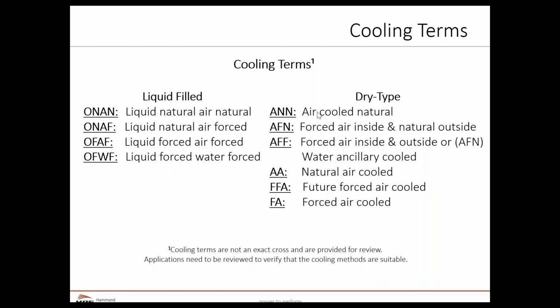There are different terms. Liquid filled has ONAN, ONAF, OFAF, OFWF. Those aren't directly attributable to the terminology that we use for dry type transformers. So if we see an ONAN, we don't necessarily have a direct equivalent. I guess the closest one for us would probably be AN, but again, different terms, and in some cases different methods to do the cooling. I'm not going to go into all of these, but just be aware when we see these cooling terms that start with an O on the left-hand side of this chart, we know pretty much that this was a liquid-filled specification.